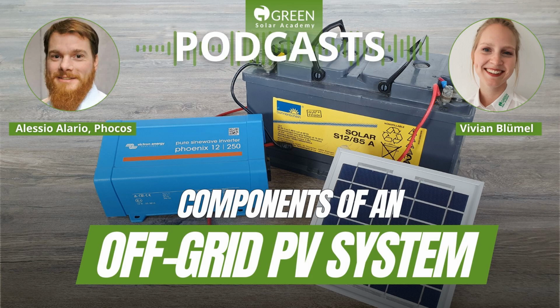And what does MPPT stand for? Maximum power point tracking. So it's looking at what the maximum watt output of your PV module is by essentially varying the voltage and the current. It just makes sure that your PV module is operating at its best possible potential. And a PWM charge controller cannot do that. It can only either not take power or essentially connect the PV modules so they run at the same voltage as the battery.